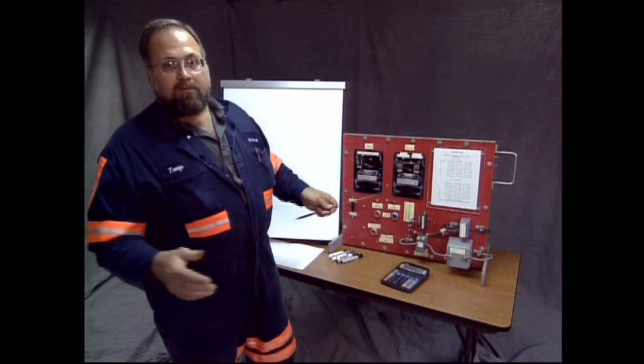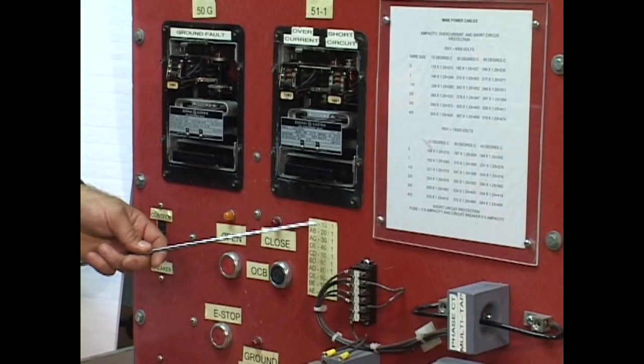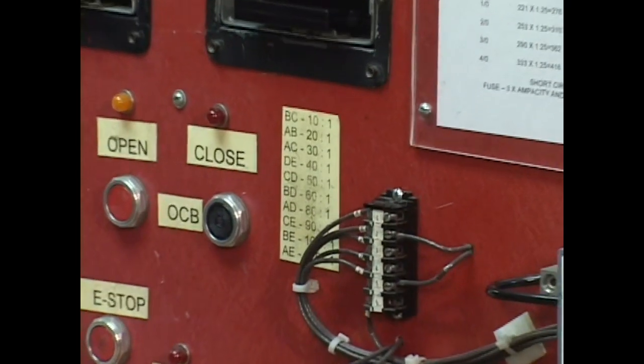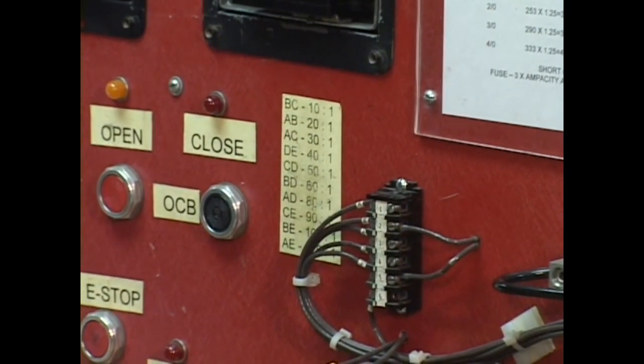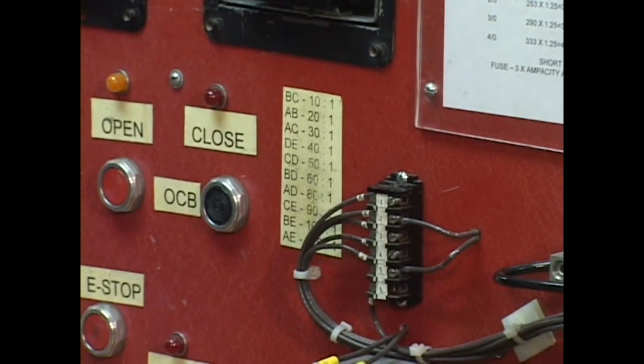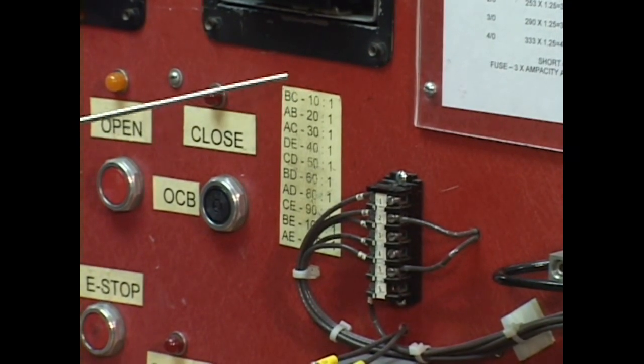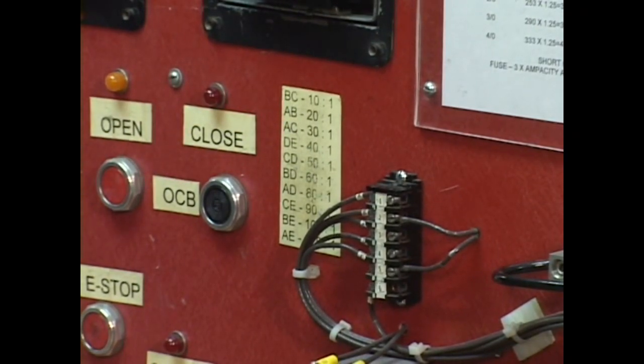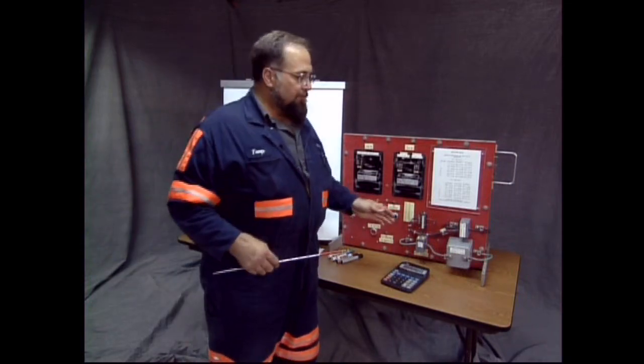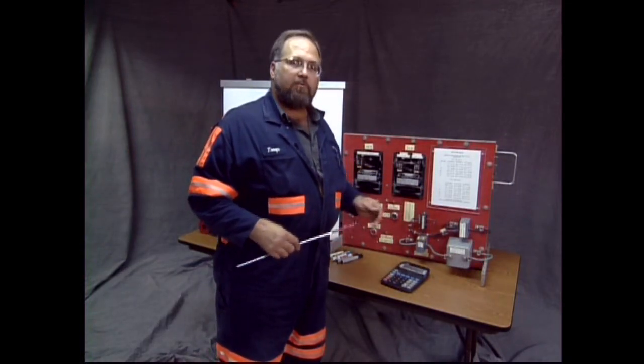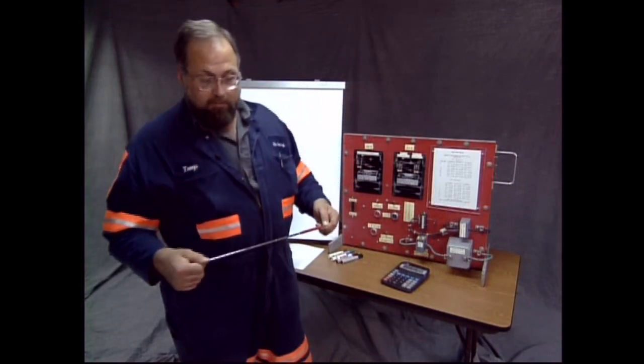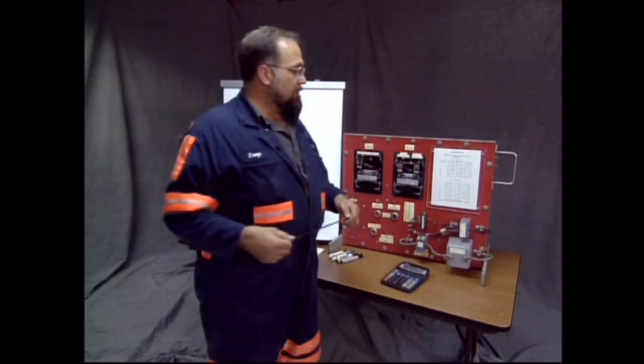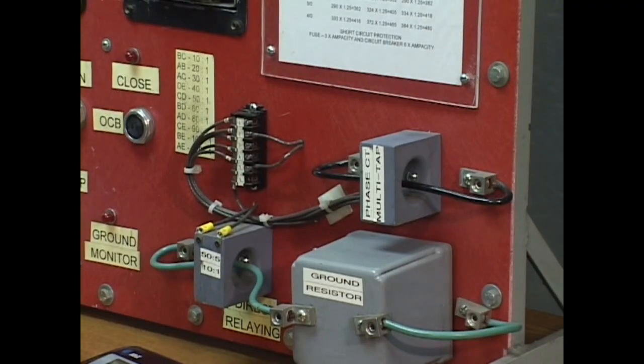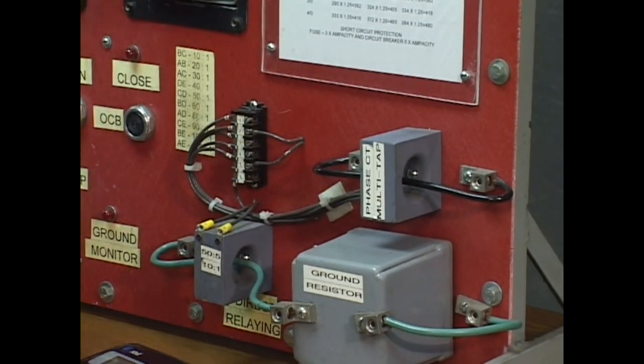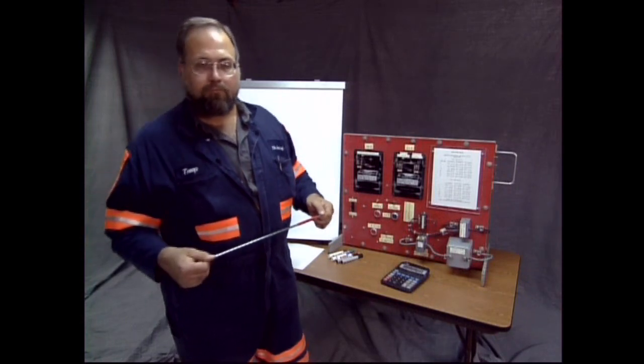Now, for the ease of our math, these relays are expressed in simple ratios, at its most simple form, 10 to 1. You won't find a 10 to 1 relay. The second number will almost invariably be a 5. You'll have a 50 to 5, a 100 to 5, 150 to 5. And the reason we use that 5 is that the 5 illustrates the ampacity of the secondary of the CT. There's an industrial standard for the ampacity of these CTs, these current transformers. CT is an acronym for current transformer. The industrial standard is 5 amps for the secondary.